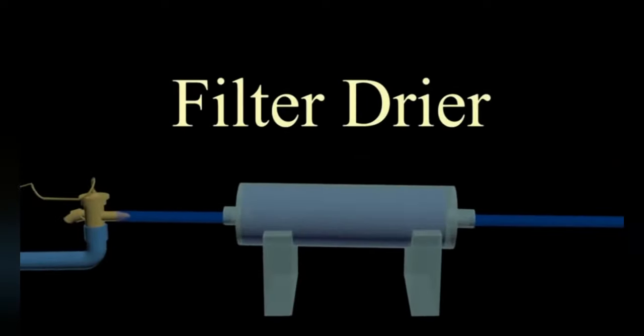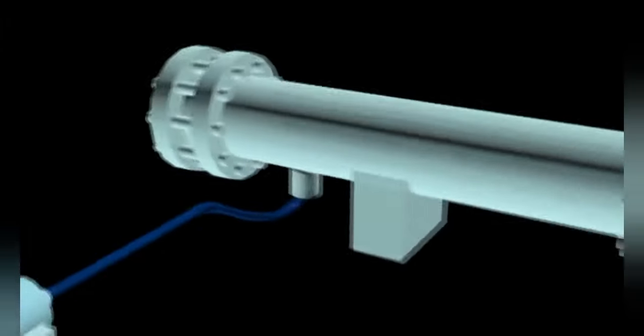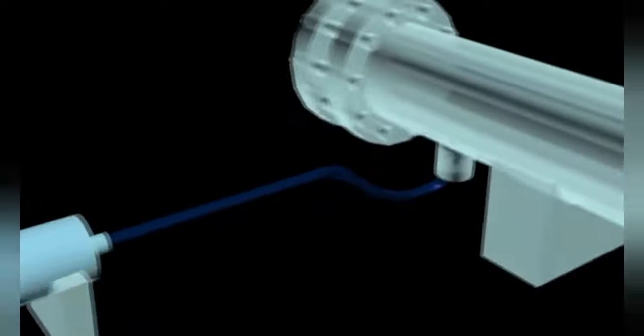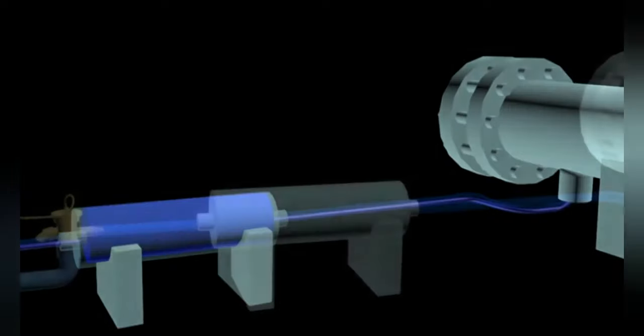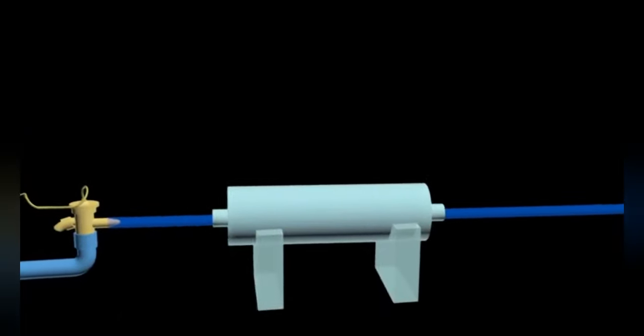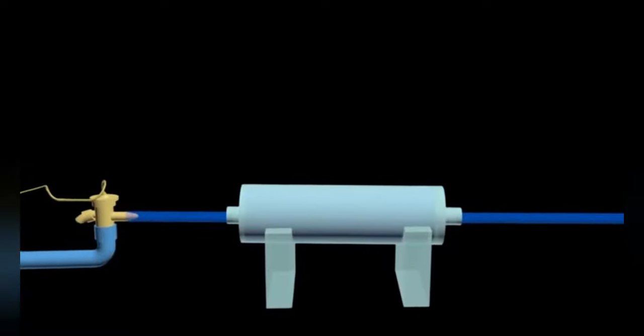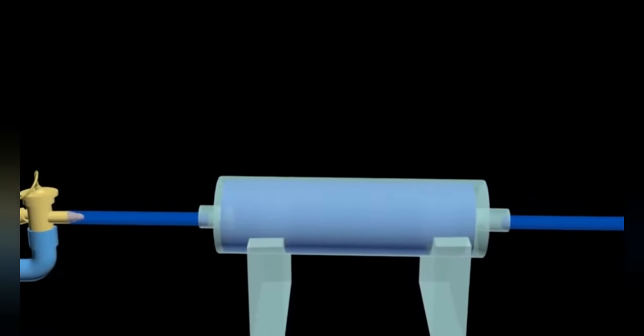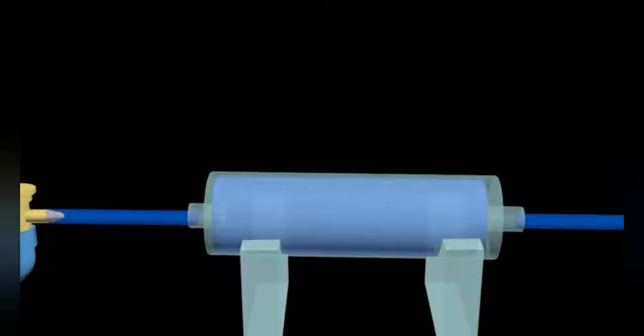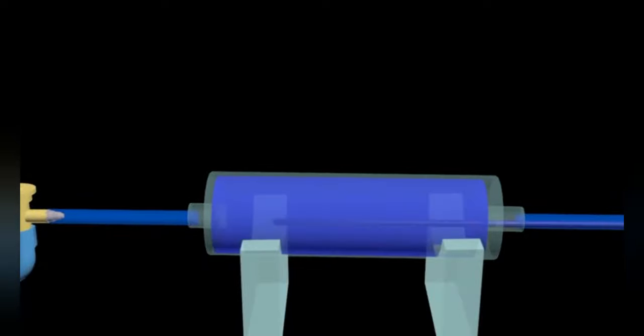Before the refrigerant flows to the next main component, it passes through an additional component called the filter dryer. The dryer acts as a dirt filter and absorbs any moisture present in the refrigerant, ensuring the refrigerant is clean and dry before entering the expansion valve.